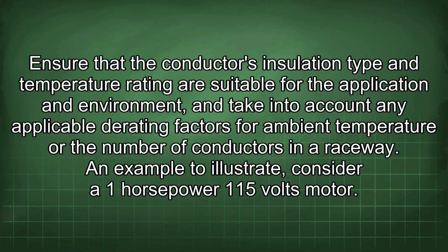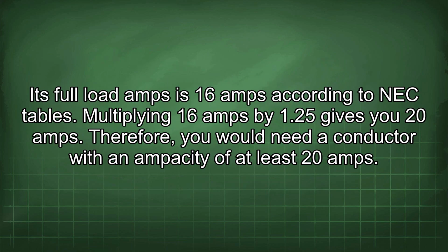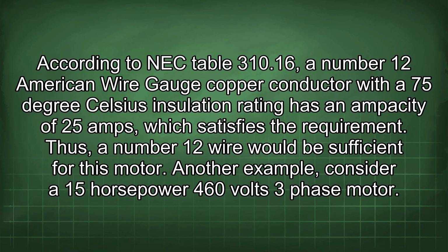An example to illustrate: consider a 1 horsepower 115 volts motor. Its full load amps is 16 amps according to NEC tables. Multiplying 16 amps by 1.25 gives you 20 amps. Therefore, you would need a conductor with an ampacity of at least 20 amps. According to NEC Table 310.16, a number 12 American wire gauge copper conductor with a 75 degrees Celsius insulation rating has an ampacity of 25 amps, which satisfies the requirement. Thus, a number 12 wire would be sufficient for this motor.